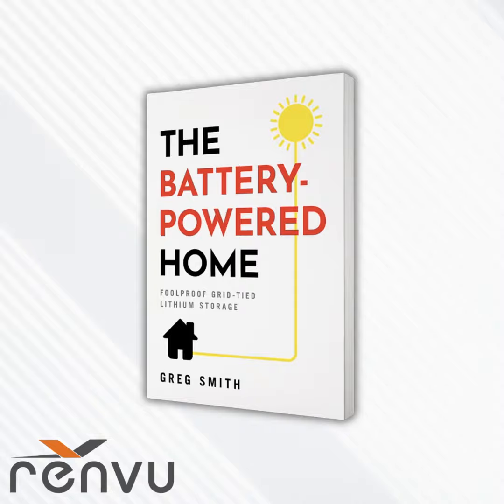So let's contrast that with a whole home backup. This is one way to do it: we put the automatic transfer switch between the meter and the main lugs of the main service entrance. This may or may not be practical depending on your main panel, but there are new products called meter collars.